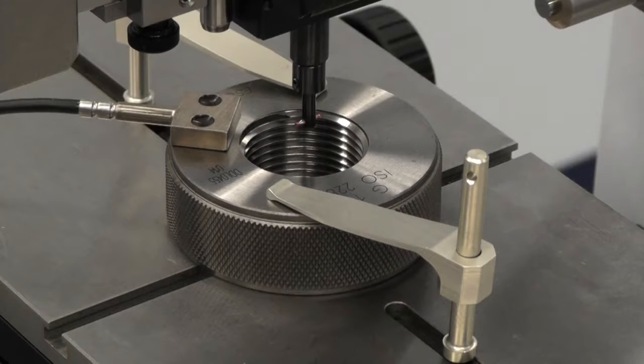Internal thread rings are a simple matter with the Labconcept Nano. For this application, the internal measuring device is outfitted with a T-shaped ruby ball probe. As with the thread wires, QMsoft holds a database of available probe ball diameters. Given the thread dimensions, the software will select the best available probe to measure the pitch diameter. This setup also shows the magnetic temperature compensation sensor.